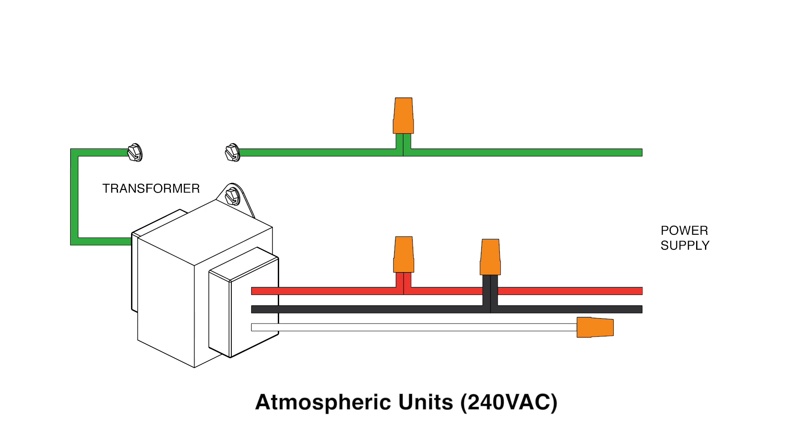Strip back the ends of the incoming wires as well as the black, red, and green wires from the transformer. Attach the incoming black wire to the black wire from the transformer using a wire nut. Attach the incoming red wire to the red wire from the transformer. Attach the green ground wires. Use a wire nut to terminate the white wire.